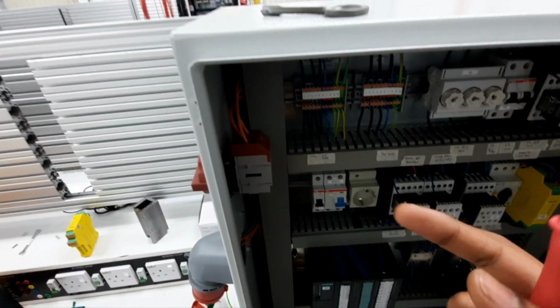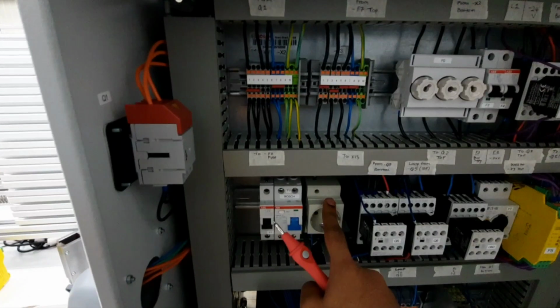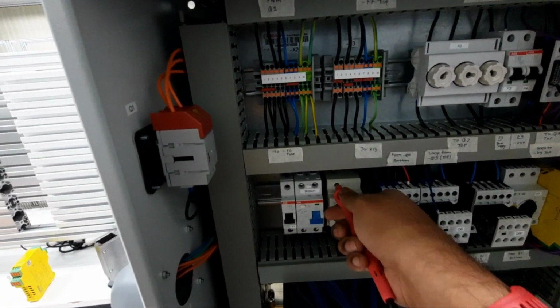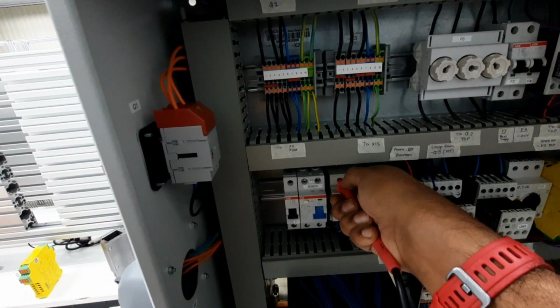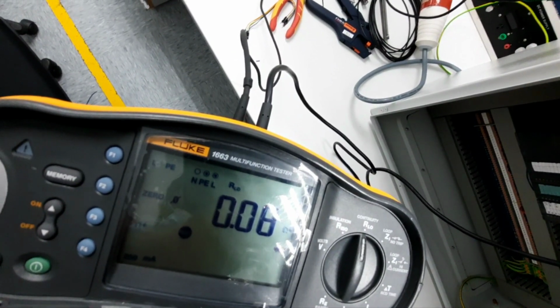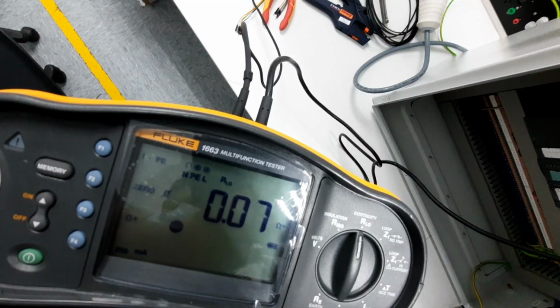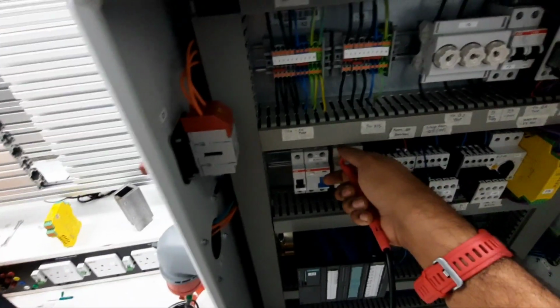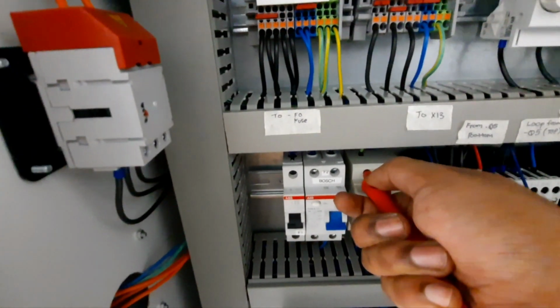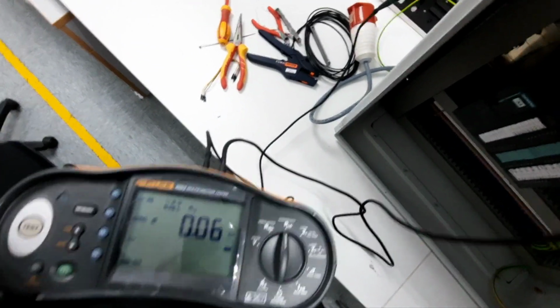And then what you need to do is this one. For your staging list, it says continuity of protective conductor means X11. So you press this one, go to here, then you test. I got 0.09, so you might get something like 0.1, but the condition is it must be less than 0.3, so this is okay. I don't have a mechanical here because they took it already, but it's at the back there. For protection, this one is actually for X11, and I got 0.06, so done.